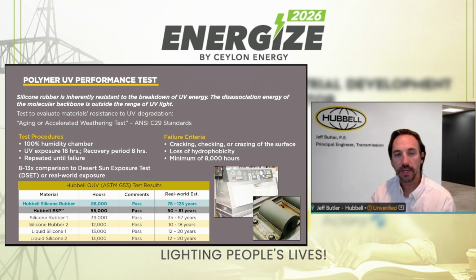So we took plaques of rubber, put them inside this chamber, and tested them until we saw some sort of failure. And the failure criteria was cracking, checking, crazing of the surface, basically a breakdown of the polymer itself, extended loss of hydrophobicity, and then our threshold was a minimum of 8,000 hours. So we took our Hubbell silicone rubber, our Hubbell ESP, two other silicone rubbers, and two other liquid silicones, and we performed the test. Successfully, all of them did pass the 8,000 hour minimum, but you can see there that the Hubbell materials far exceeded the others.